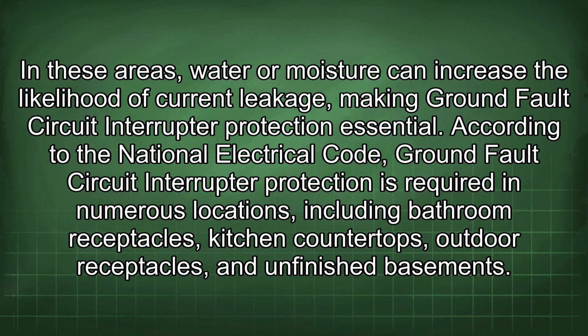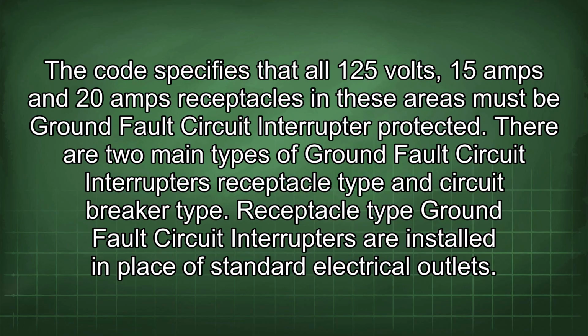According to the National Electrical Code, ground fault circuit interrupter protection is required in numerous locations, including bathroom receptacles, kitchen countertops, outdoor receptacles, and unfinished basements. The code specifies that all 125 volt, 15 amp and 20 amp receptacles in these areas must be ground fault circuit interrupter protected. There are two main types of ground fault circuit interrupters: receptacle type and circuit breaker type.